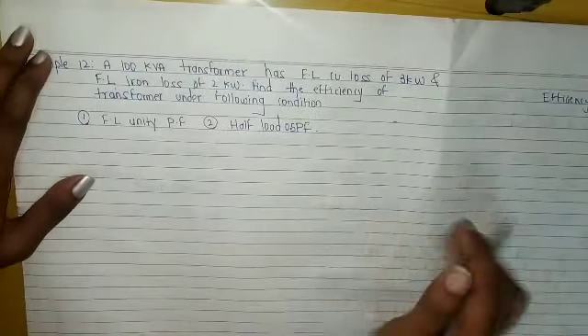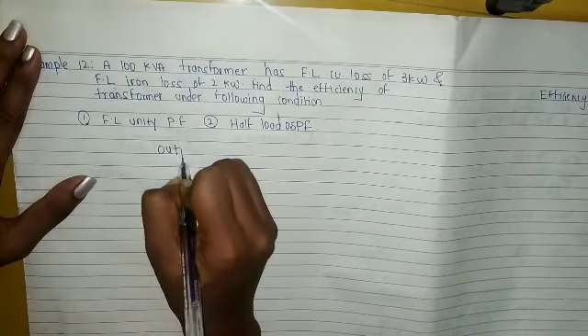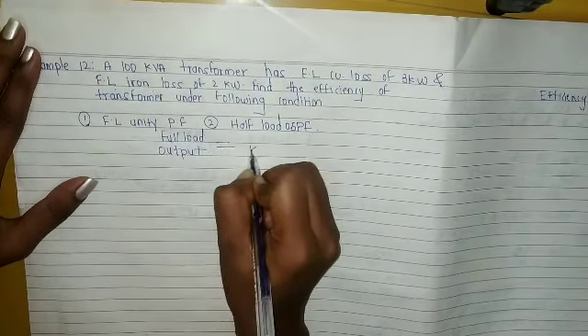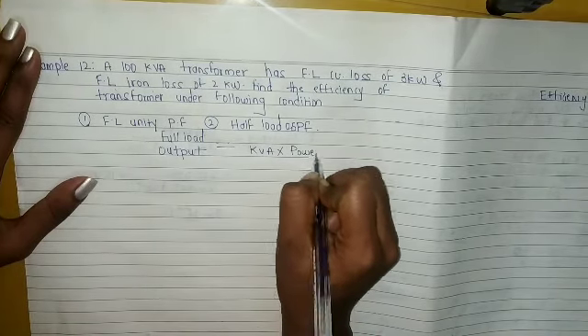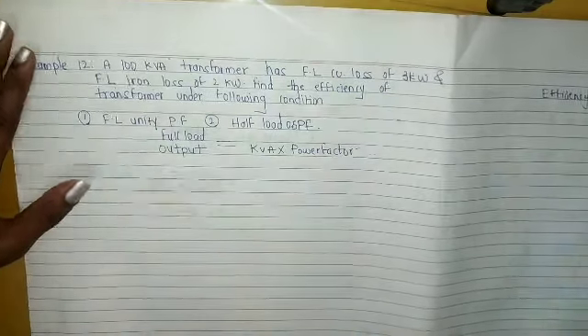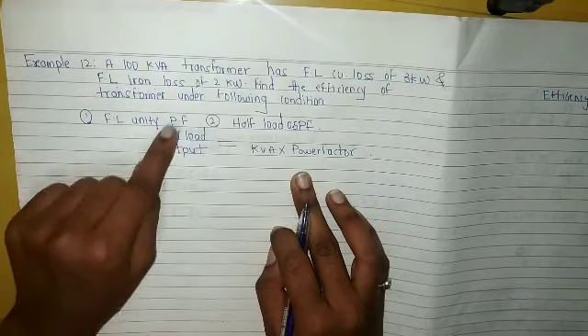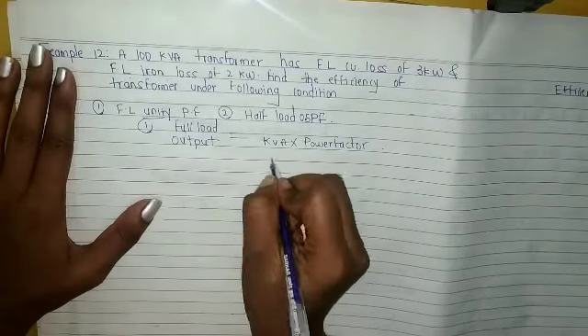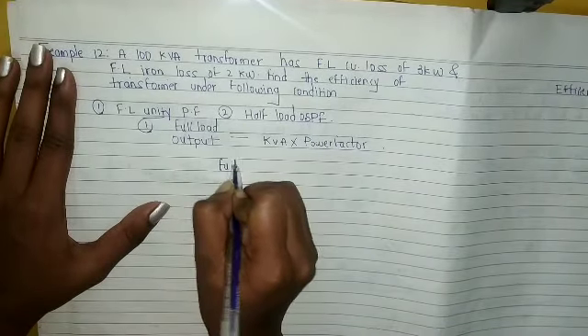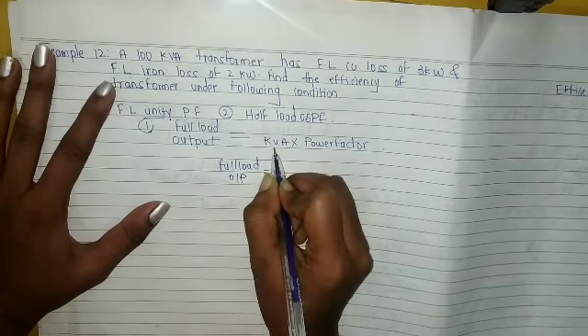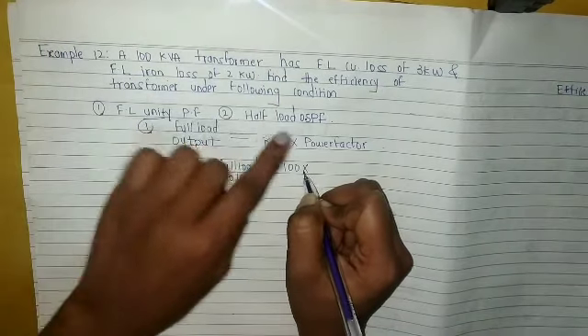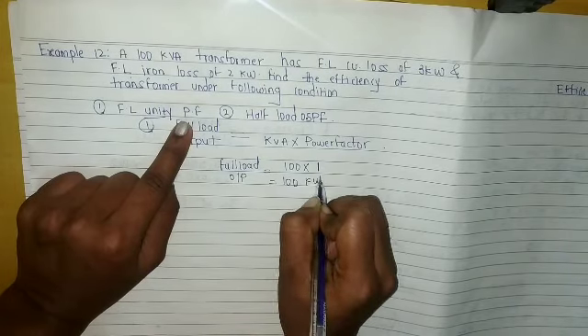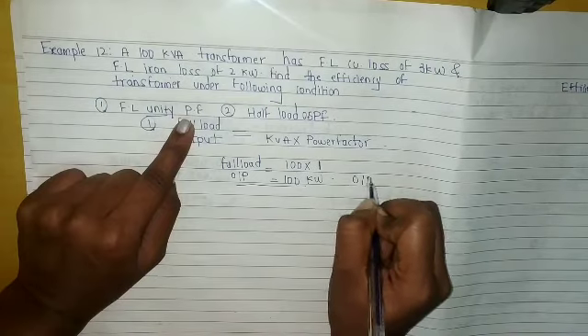The formula for full load output is kVA multiplied by power factor. They have given 100 kVA and unity power factor, which means 1. Substituting the values: full load output equals 100 into 1, which gives us 100 kW.